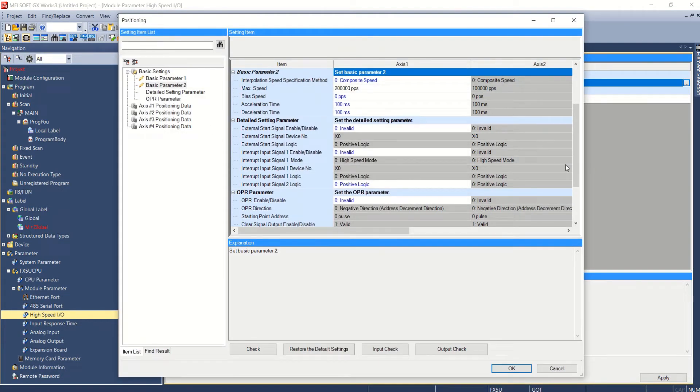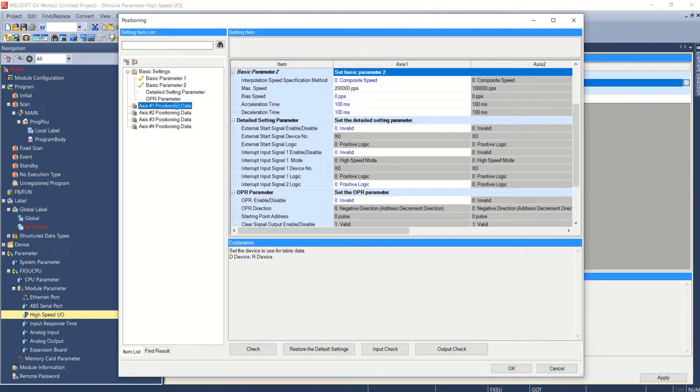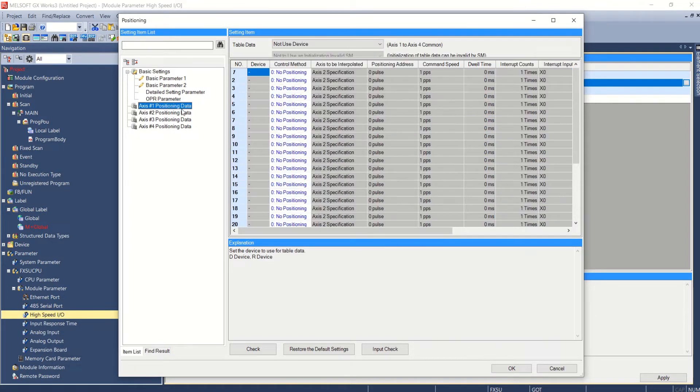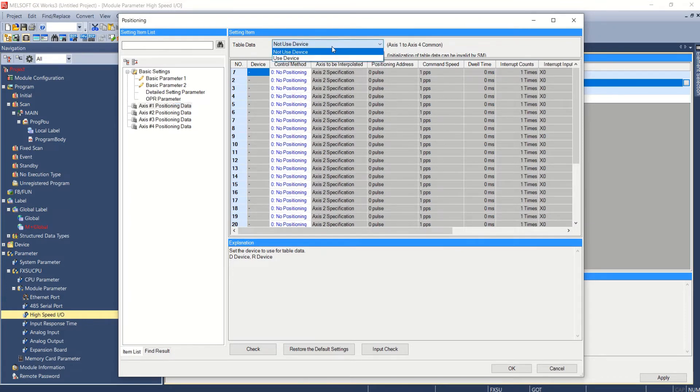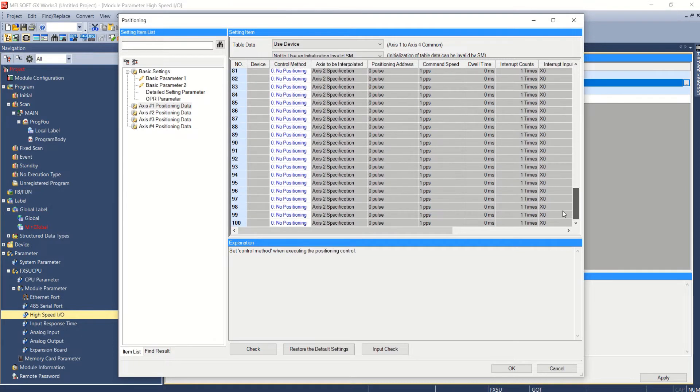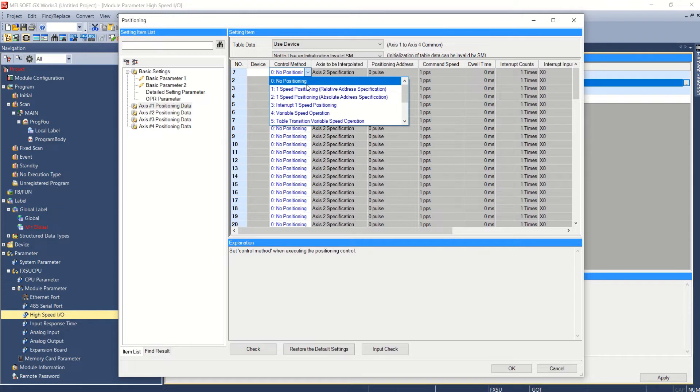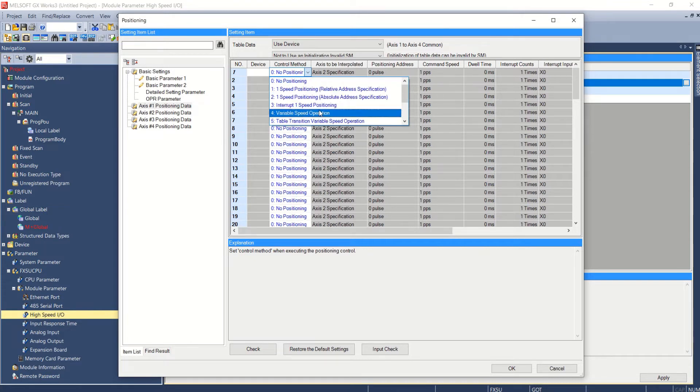Now you can run servo motor by two methods. First you can set tables for positioning data like here in axis number one. See here axis number one positioning data. You can set total of hundred number of tables in this setting with different control methods, one to hundred. Control methods are like relative positioning, absolute positioning, variable speed operation etc.